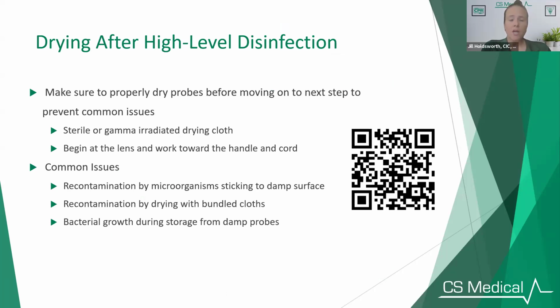So let's talk about drying. And as I'm talking, this QR code will lead you straight to a study that I'm going to be talking about. So if you'd like to go ahead and scan that, then please go ahead. Drying of the probes has to happen in two different sections. If you're manually cleaning, you must dry your probe after the cleaning step from the sink. And the reason why is because you cannot put a wet probe straight into a high-level disinfectant. You will have water droplets, you'll have some residual detergent from your enzymatic cleaning step. So the probe must be dried before you put it into that high-level disinfectant so that it doesn't make the high-level disinfectant inefficient.